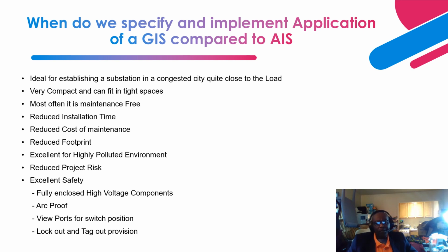Because it is compartmentalized and comes in the form of modules, if a fault should occur in a module, it doesn't escalate or transfer to the other compartments or modules. As such, the fault is much localized, and you can isolate that bay and resolve the fault.